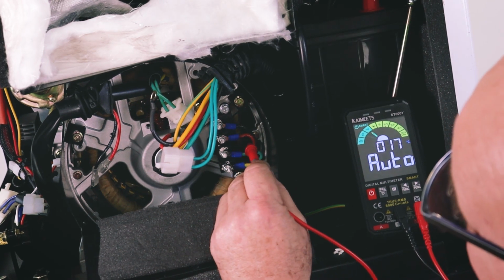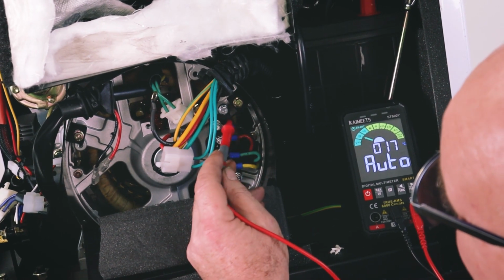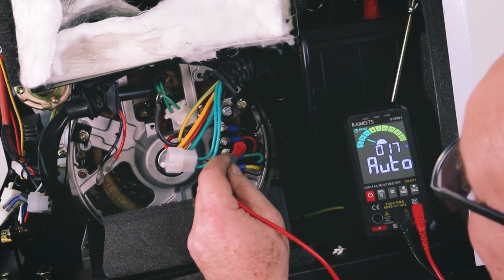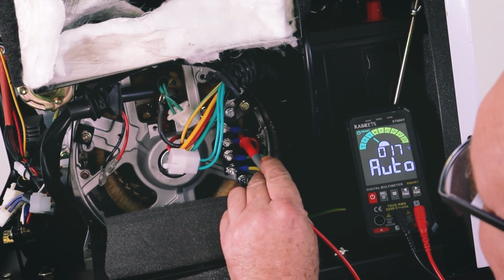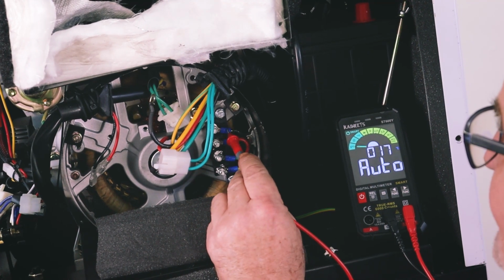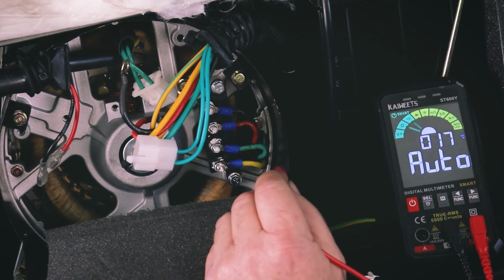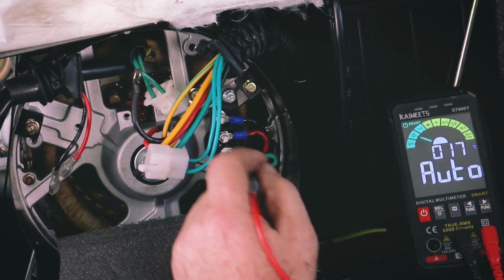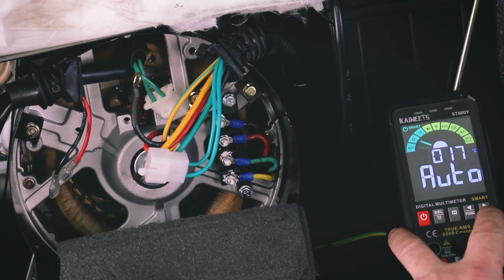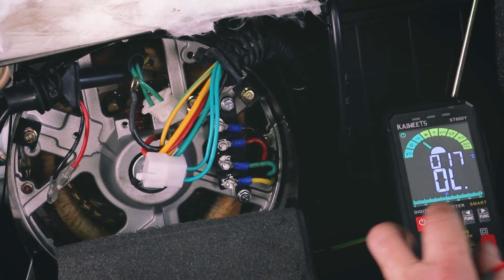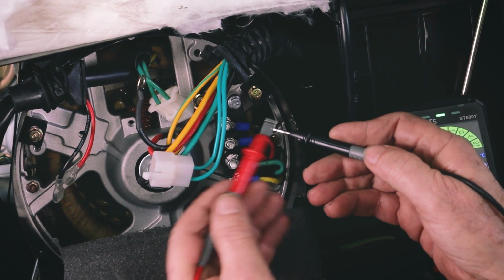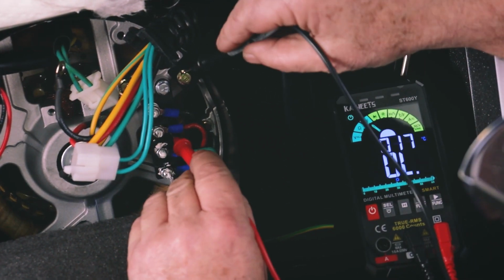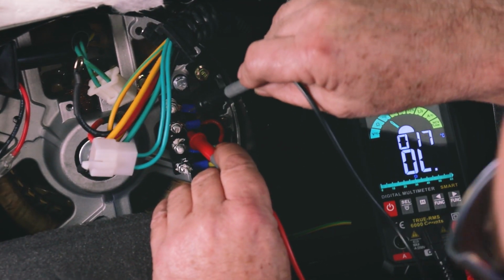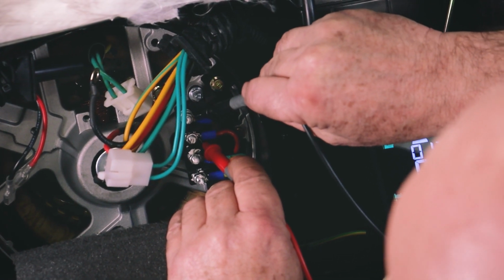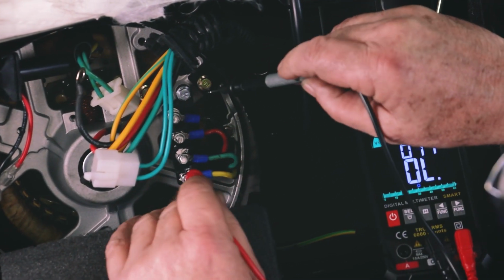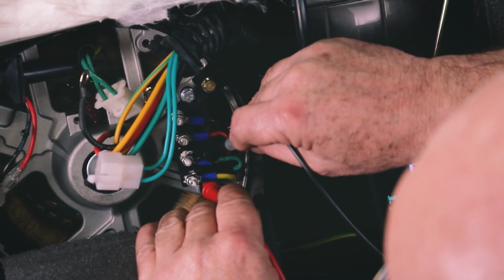So the red wire here goes into the alternator, round and round the windings for as many turns as it needs, and then comes back via the black wire. So that's the actual single winding. And again, the yellow and green will be exactly the same. So first thing I'm going to look for is continuity. So if I put my meter on a beep test, I can see we've got a beep there. Let's just make sure, and I know this is a good machine, so I should get continuity. I have continuity. I should have the same on the bottom 2.